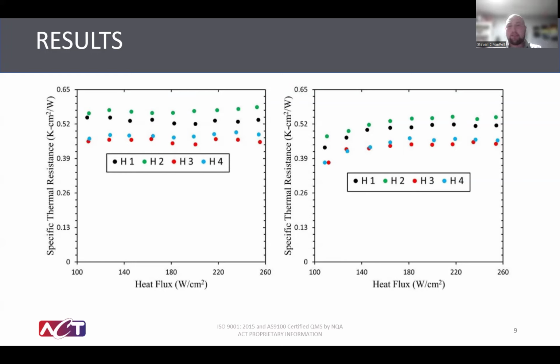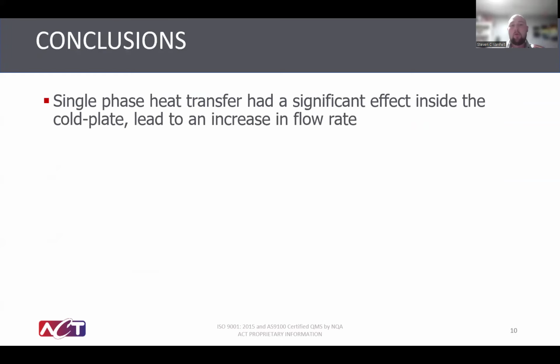Analyzing this, we asked what conclusions we could draw. We originally planned to run only at 0.5 liters per minute, but realized the single phase heat transfer had significant effects inside the cold plate, so we increased the flow rate and also ran it at 1 liter per minute.